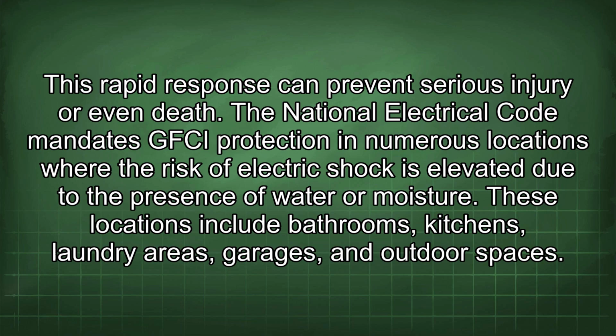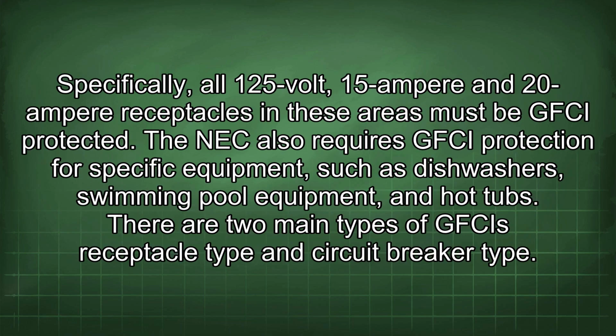The National Electrical Code mandates GFCI protection in numerous locations where the risk of electric shock is elevated due to the presence of water or moisture. These locations include bathrooms, kitchens, laundry areas, garages, and outdoor spaces. Specifically, all 125-volt, 15 ampere and 20 ampere receptacles in these areas must be GFCI protected. The NEC also requires GFCI protection for specific equipment, such as dishwashers, swimming pool equipment, and hot tubs.